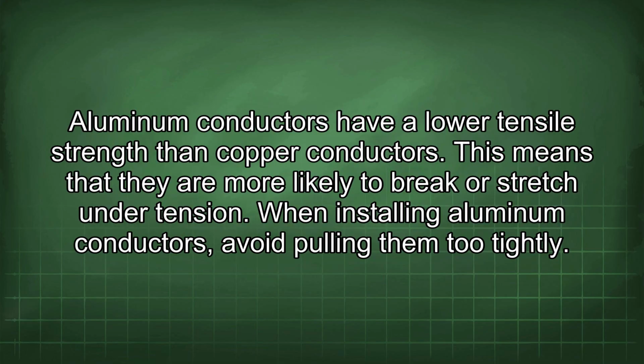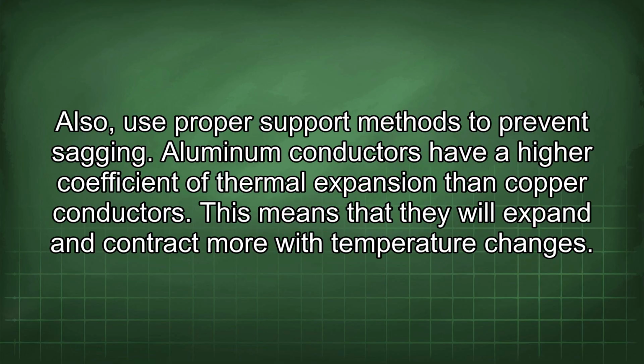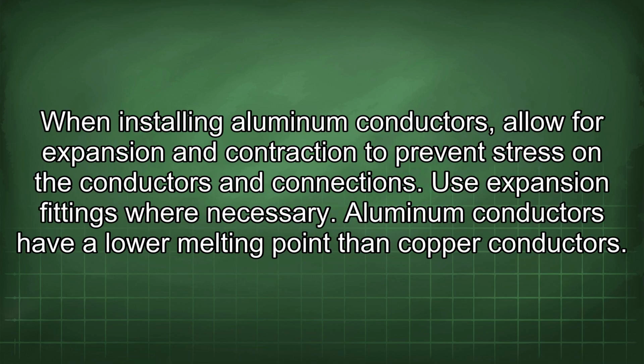Aluminum conductors have a lower tensile strength than copper conductors. This means that they are more likely to break or stretch under tension. When installing aluminum conductors, avoid pulling them too tightly. Also, use proper support methods to prevent sagging. Aluminum conductors have a higher coefficient of thermal expansion than copper conductors. This means that they will expand and contract more with temperature changes. When installing aluminum conductors, allow for expansion and contraction to prevent stress on the conductors and connections. Use expansion fittings where necessary.